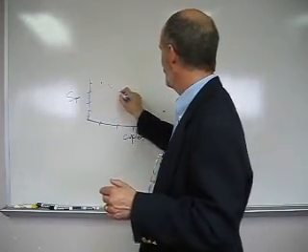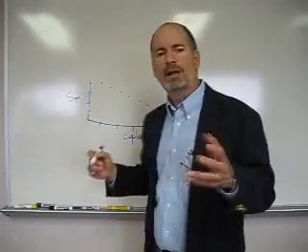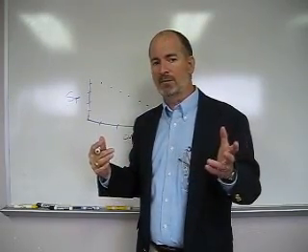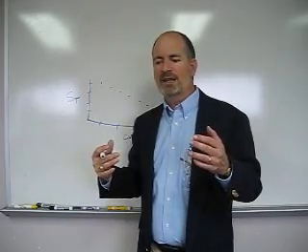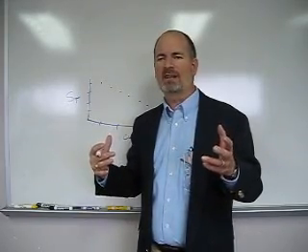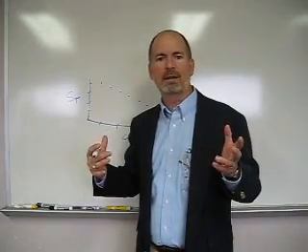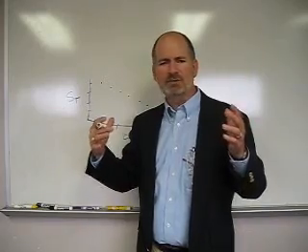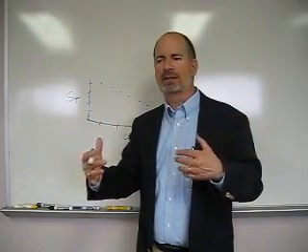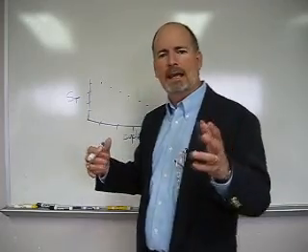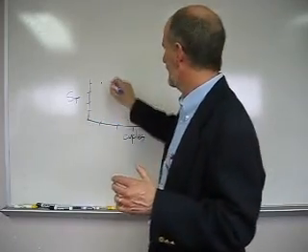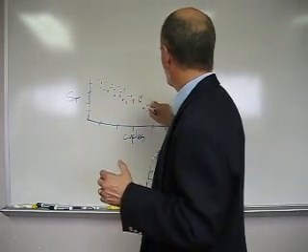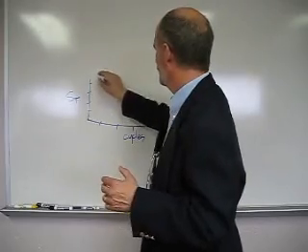And then we do that a few more times, and we're going to come up with a fatigue curve. Well, what the EJMA organization, the Expansion Joint Manufacturers Association did, was they got several manufacturers, a lot of manufacturers, about six of the companies, and they submitted lots of bellows, and they did all the testing along certain guidelines, and they all pooled all those data points, and all those data points formed a nice little pattern with blue dots all along here.